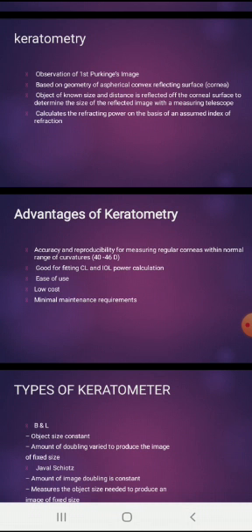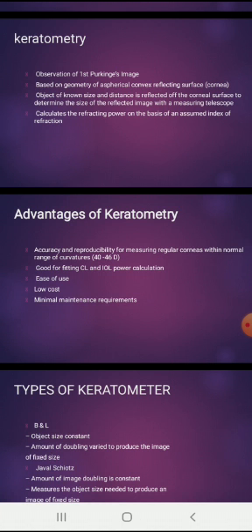In keratometry, another important thing is that we consider the corneal surface as a convex reflecting surface. We can measure the corneal radius of curvature by using the object size and image size. Either we can make the object constant and the image variable for measuring the radius of curvature, or we can make the image constant and the object variable for measuring the keratometer reading.